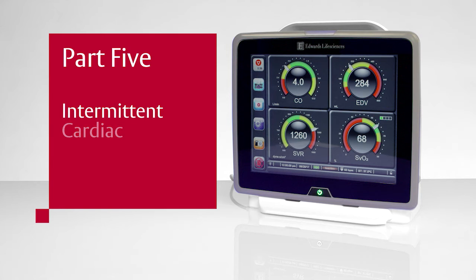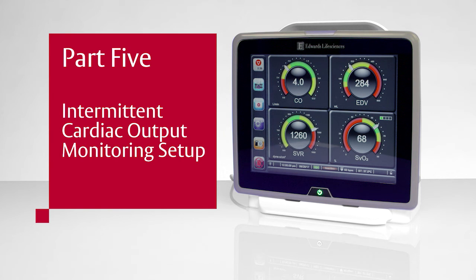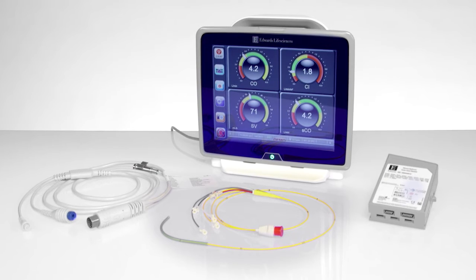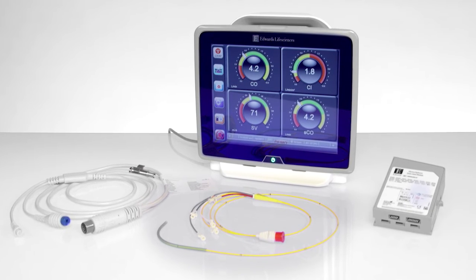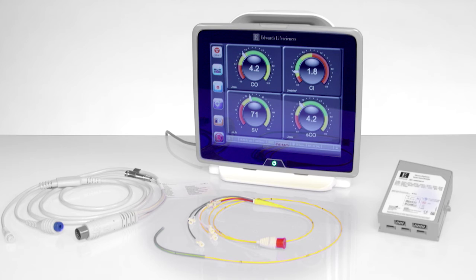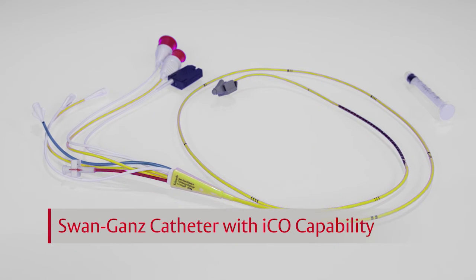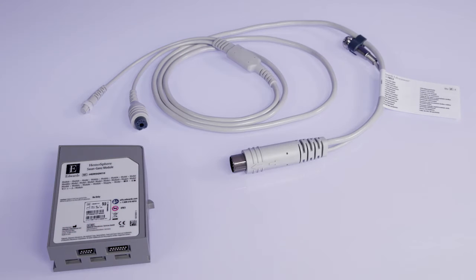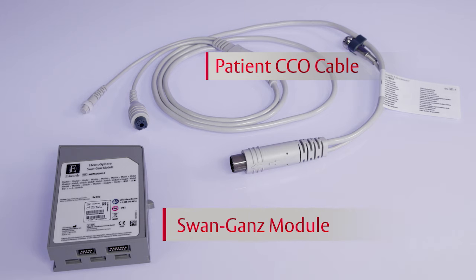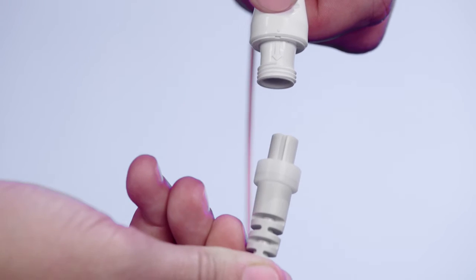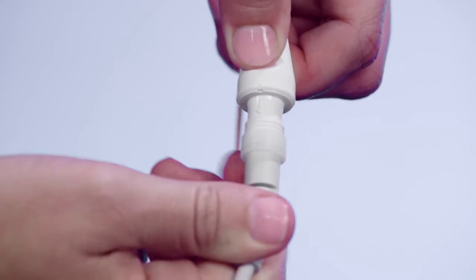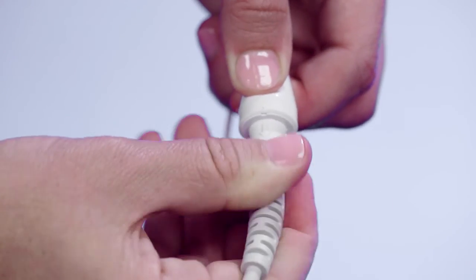Part 5. Intermittent Cardiac Output Monitoring Setup. Monitoring intermittent cardiac output with the HemoSphere Advanced Monitoring Platform requires a Swan-Ganz catheter that has ICO capability. In addition, you will need the patient CCO cable with a temperature probe, inline or bath, and the HemoSphere Swan-Ganz module. Attach the catheter end of the patient CCO cable to the thermistor connector on the Swan-Ganz ICO catheter.